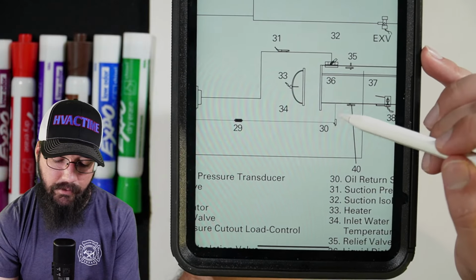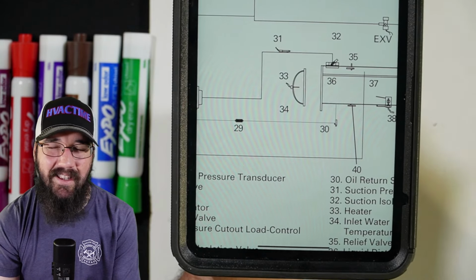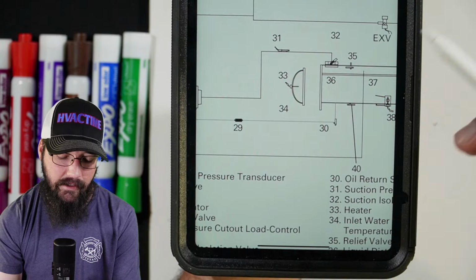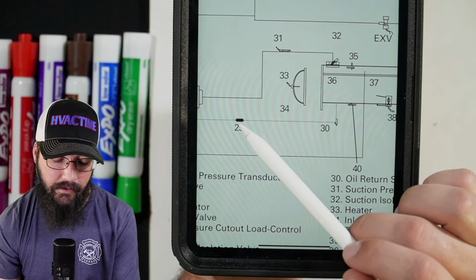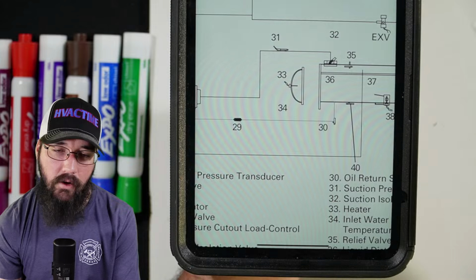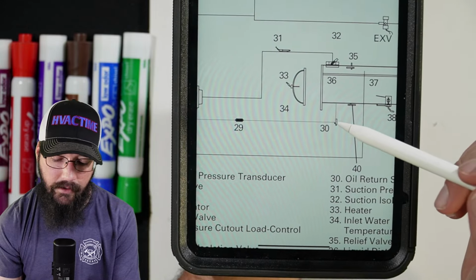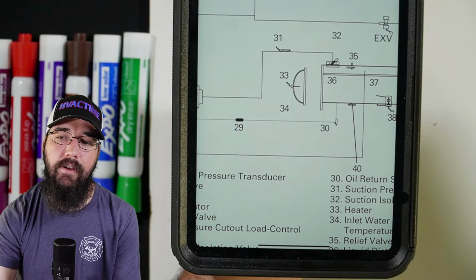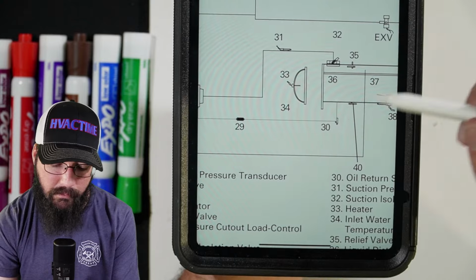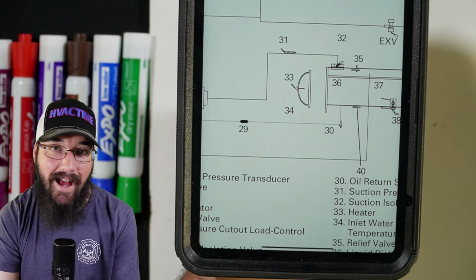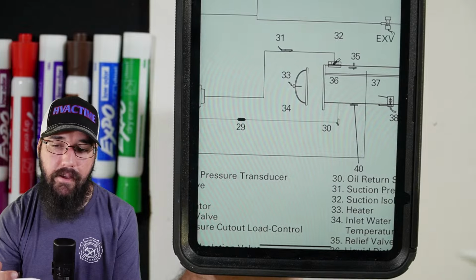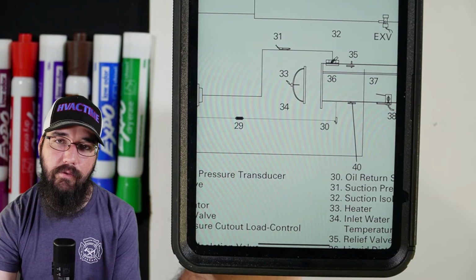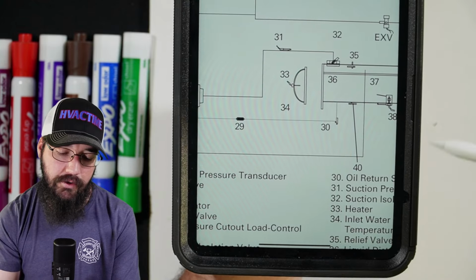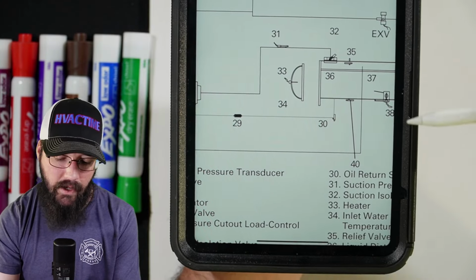You could just have some kind of debris maybe get in the way. I'd say it's far less likely. It's far more likely, in my opinion, that this dryer or this valve are going to be your primary issue, and that's going to be preventing you from flowing back into the compressor. Those are the main areas I would want to be paying attention to if I thought, or if I knew, that I was having an oil return issue causing it to stack in the evaporator.